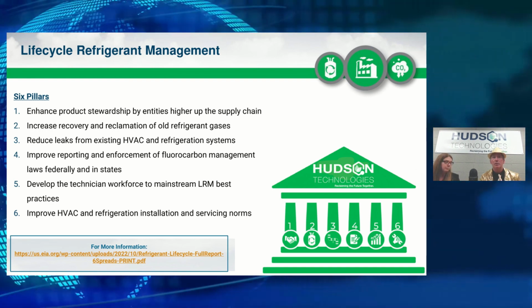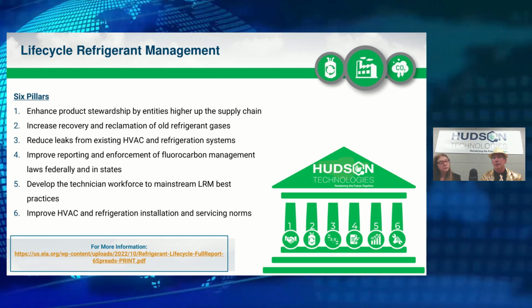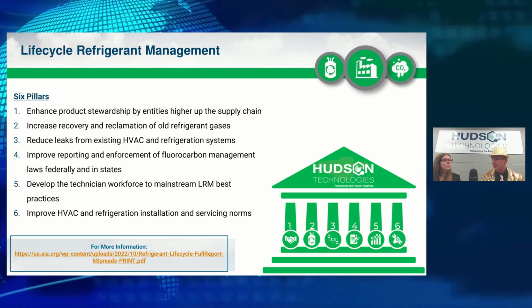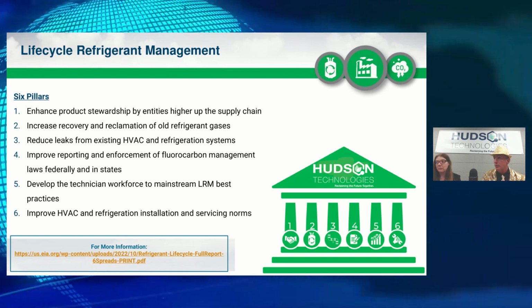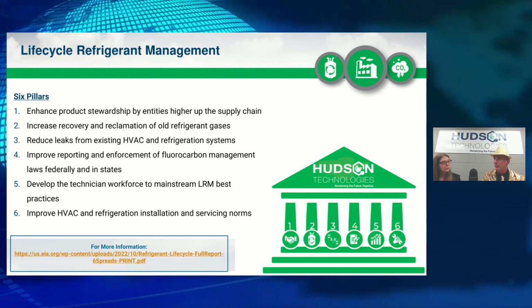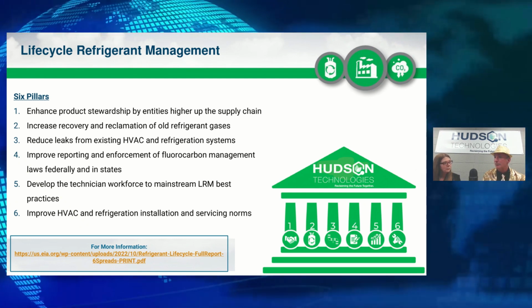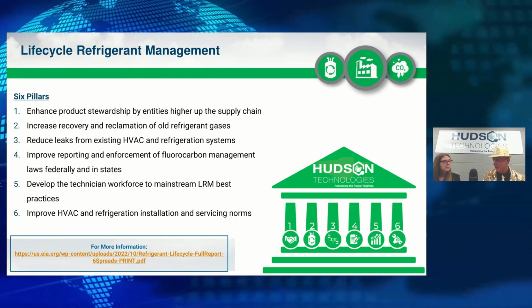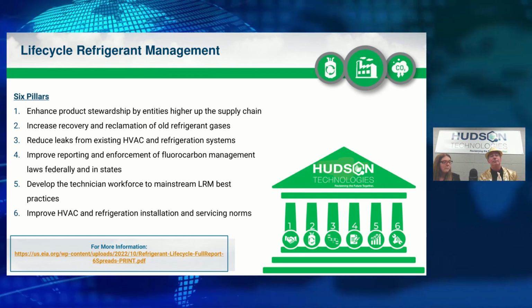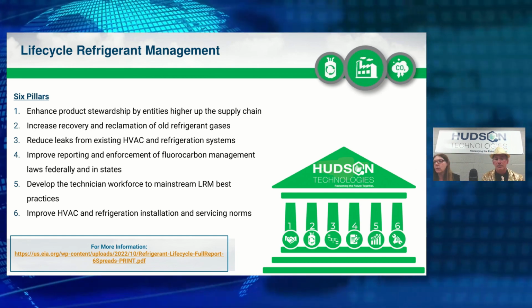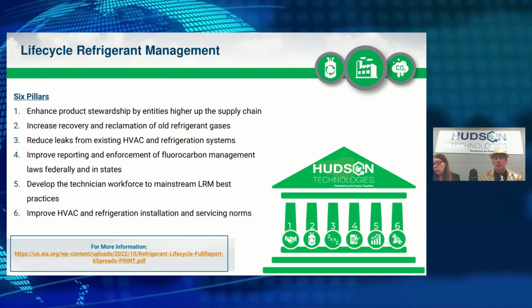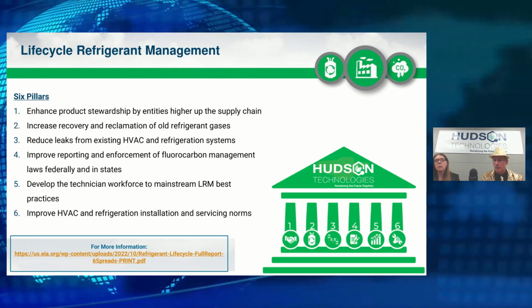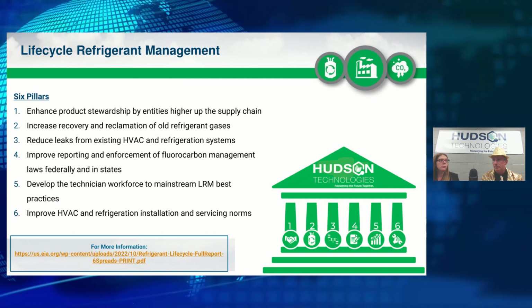You got it. It really becomes this circularity, and the only way to keep that system running is going to be 404. What's interesting, if we pick on 404, is that it's a refrigerant in commercial refrigeration that's frequently, because it stays with that system owner, not reclaimed but reused by owners.